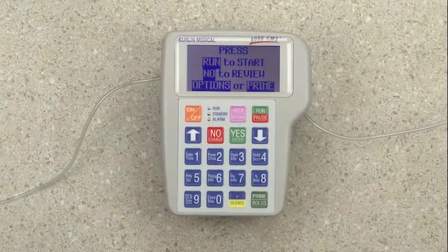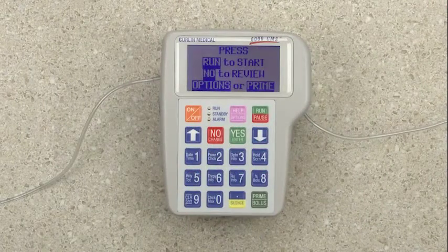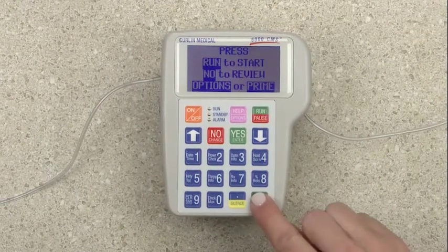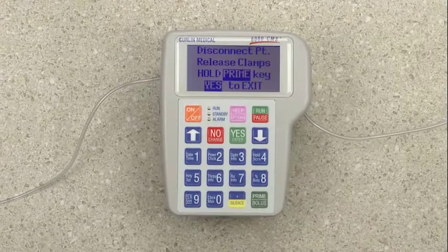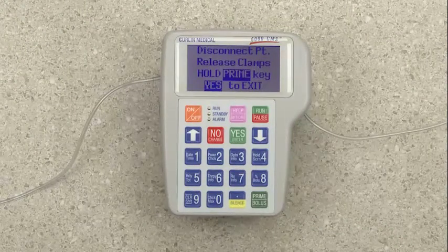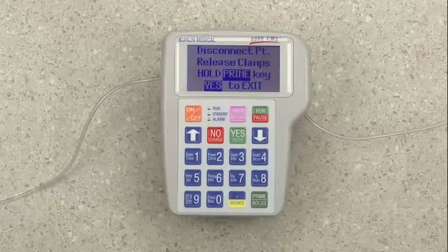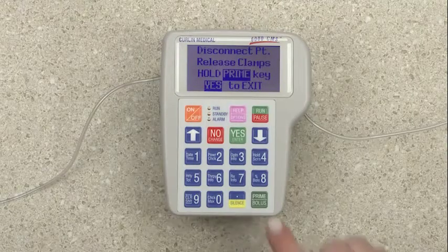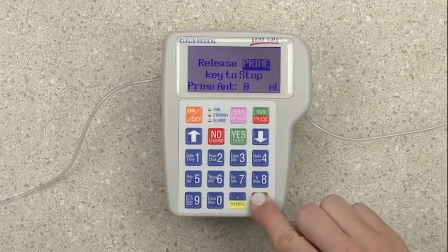From the Run to Start screen, we can prime the air out of the tubing by pressing the Prime key and following the instructions on the screen. These instructions include disconnecting the line from the patient, release any clamps on the line, and hold the prime until the air has passed out of the tubing.